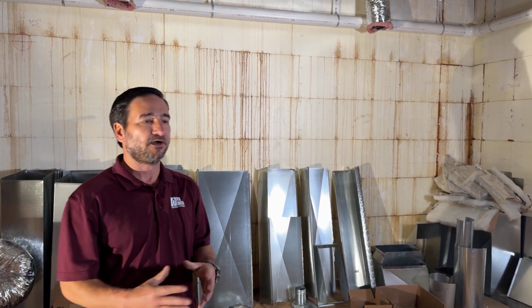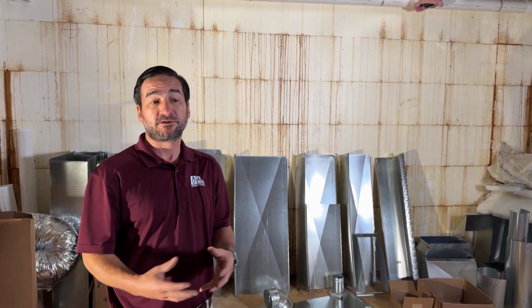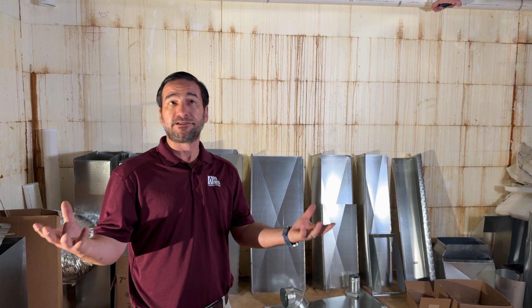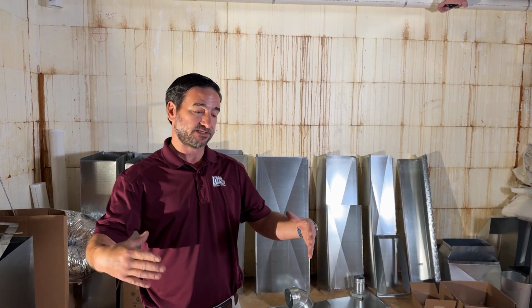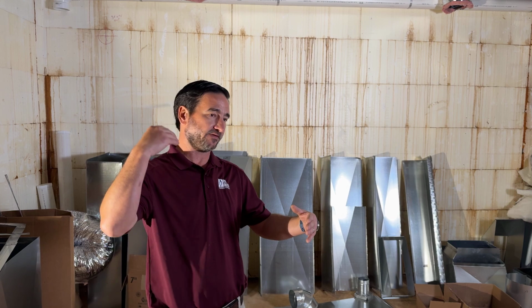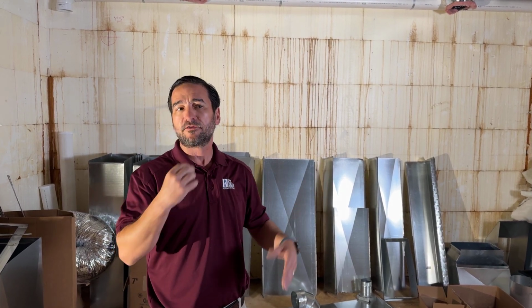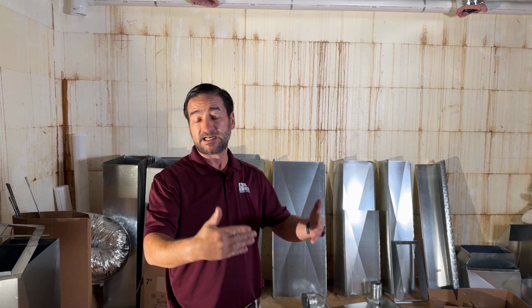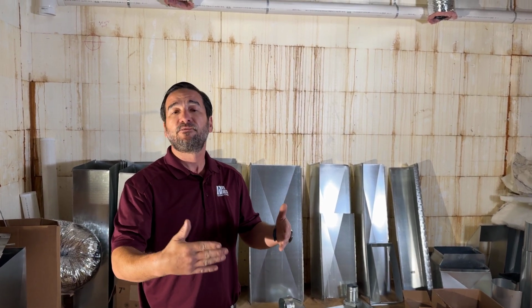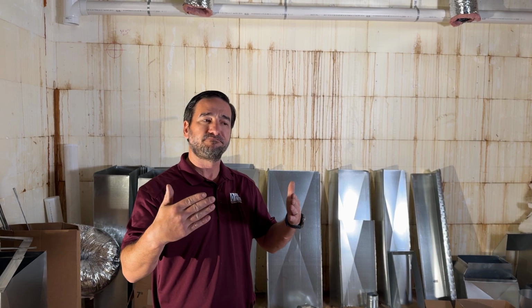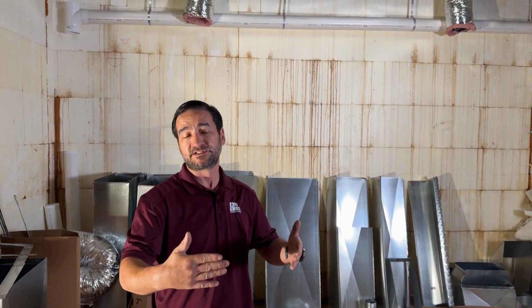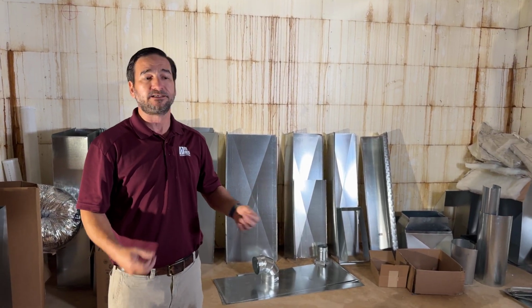Right. So I always kind of explain it by, if we come to your house to replace your piece of equipment, we are supposed to do a load calculation. If you already have ductwork in your home, we're supposed to do a block load. So we are essentially saying, okay, computer, you have this much wall and window that face west and this much east, north, south, and the wall is of this construction. It either has insulation or it doesn't. Essentially, we are computing how much heat loss or gain there is through the construction materials of the house. It doesn't have as much to do about volume, it has more to do about exposure. So when we do that load calculation, we say, how much energy does it take to keep your thermostat at 75 degrees when it's 93 degrees outside? And it gives us a number.